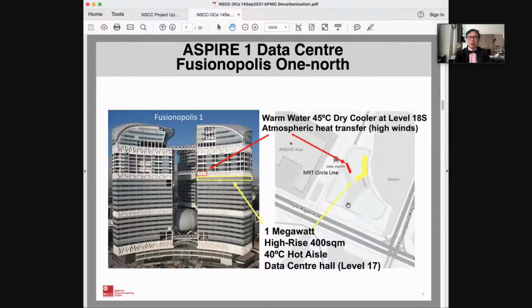In Singapore, we're a very small country, and high rise is the way forward. Our supercomputer is at level 17, and we make use of the fact that it's high rise to tap on the strong winds up there. As a result, we're able to run our data center hot—our hot aisle is actually 40 degrees. Because the temperature outside is at most 35 to 36 degrees due to global warming, the temperature differential is still sufficient for us to effect a heat transfer of 45 degrees at level 18, the red colored dotted box where we expel heat into the upper atmosphere.